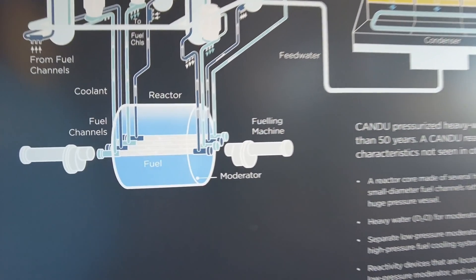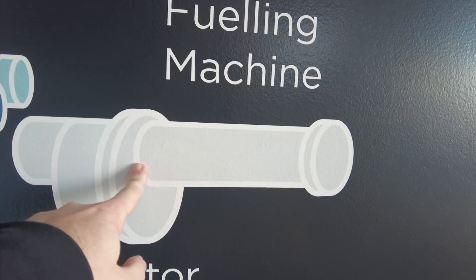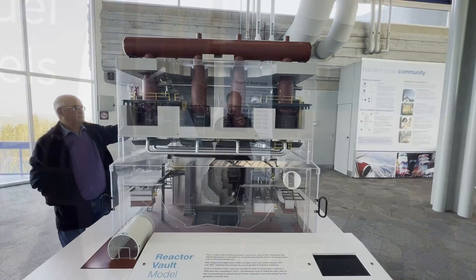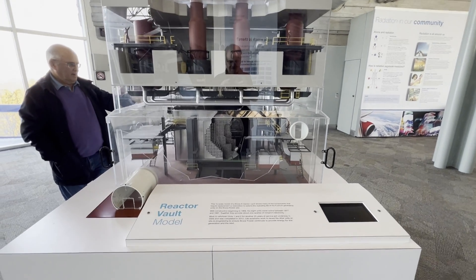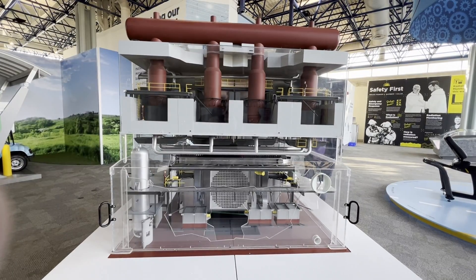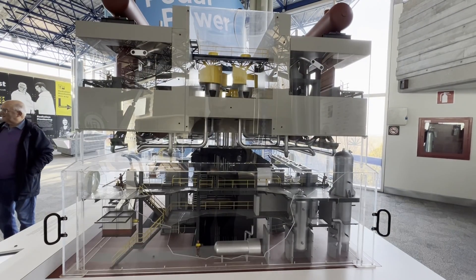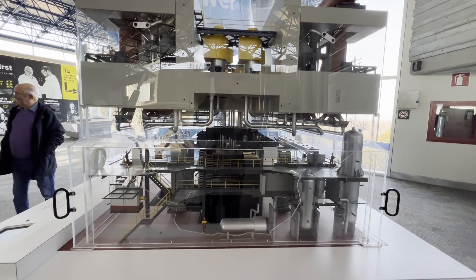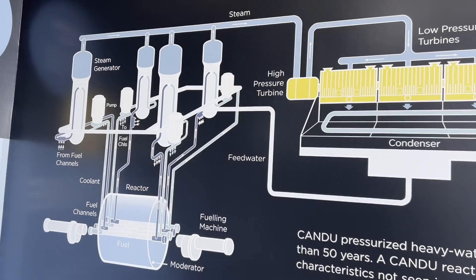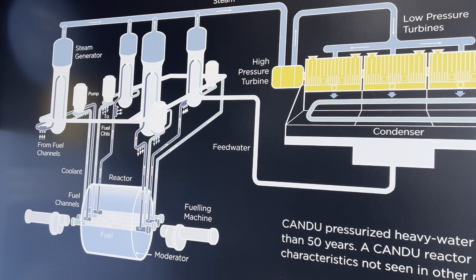So you've got the fuel channels here, fuel, moderator, fueling machine, fuel bundles, and then your fuel channel. CANDU pressurized heavy water reactors have been safely operating for more than 50 years. The CANDU reactor has a number of unique design features not seen in other reactors: a reactor core made of several hundred small diameter fuel channels rather than one huge pressure vessel; heavy water D2O for both the moderator and coolant; two separate low pressure moderator and high pressure fuel cooling systems; reactivity devices located in the cool low pressure moderator not subject to high temperatures; and natural uranium fuel.